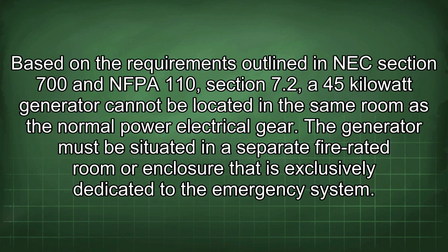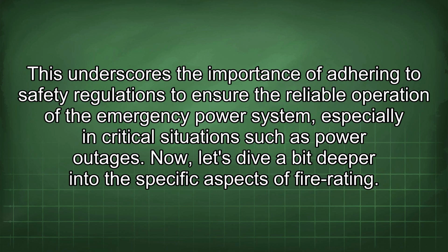Based on the requirements outlined in NEC Section 700 and NFPA 110 Section 7.2, a 45 kW generator cannot be located in the same room as the normal power electrical gear. The generator must be situated in a separate fire-rated room or enclosure that is exclusively dedicated to the emergency system. This underscores the importance of adhering to safety regulations to ensure the reliable operation of the emergency power system, especially in critical situations such as power outages.